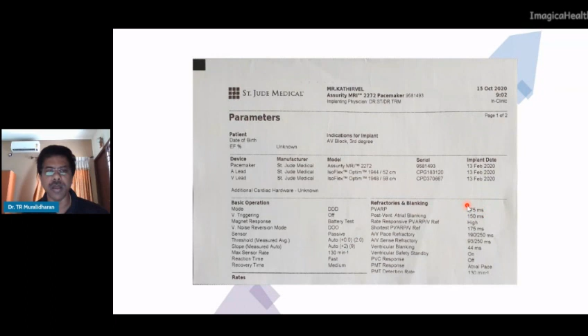So pacemaker-mediated tachycardia was going on, and the atrial paced beat, which came by the intrinsic program in the device to overcome PMTs, broke the circuit and normal sinus returned. But spontaneously, because of the long AV delay he was having, with intermittent complete heart block, the tachycardia recurred within one beat. You can see here, the phenomenon was going on. So we understood that, and as I said, in him the PVARP was 275 milliseconds. We kept a long AV delay. So we changed those settings.